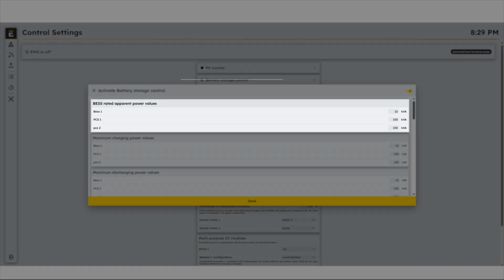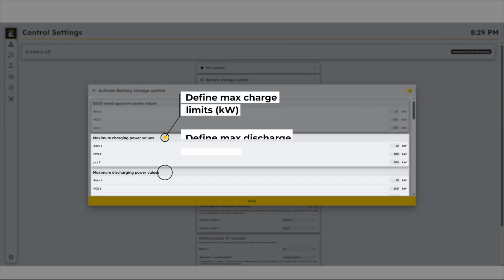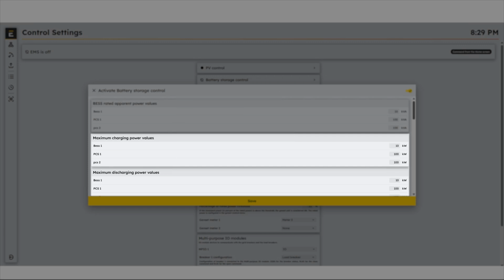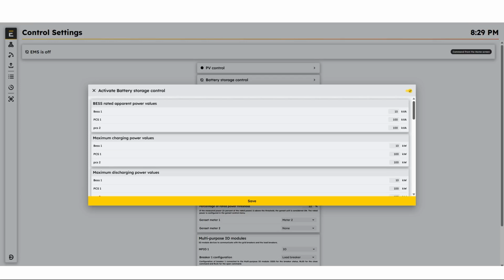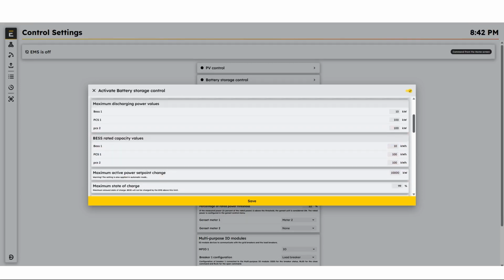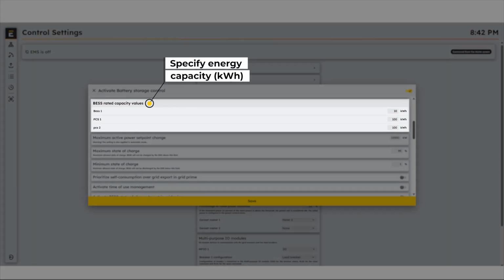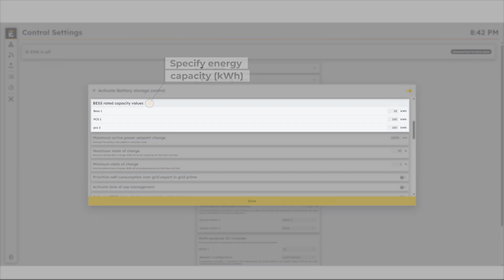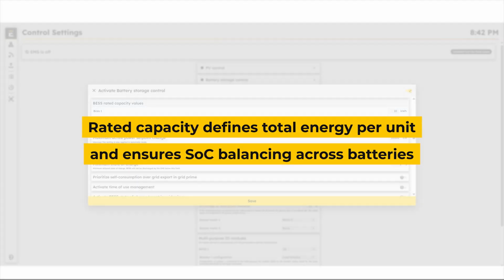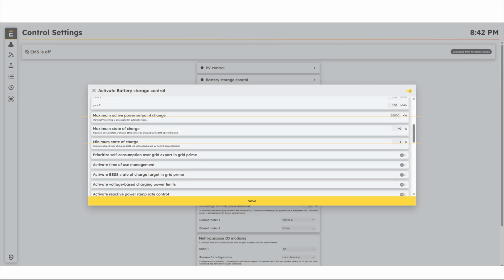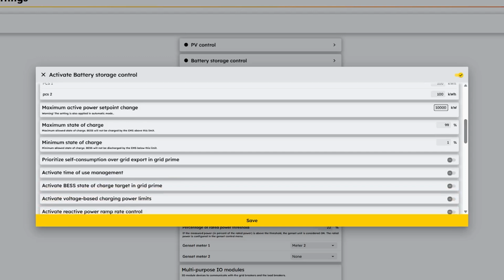The rated apparent power defines each unit's maximum active and reactive capability. The maximum charging and discharging power values ensure the EMS never sends commands beyond what the devices can safely handle. The rated capacity represents the total energy storage available per unit, a key parameter used for SOC equalization between multiple batteries, ensuring balanced operation across all units.